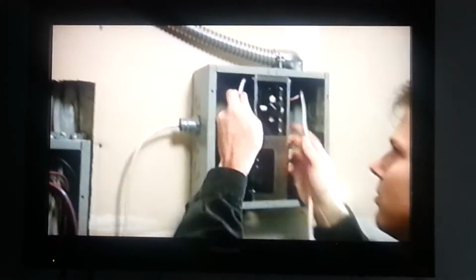Connect the other ends of the wires to the double-pole circuit breaker in the service panel, in accordance with the breaker label instructions. Please note that neutral wires from the generator or manual transfer switch should be passed through the knockouts of the ATS transfer switch to the service entrance panel. Also note that the ATS transfer switch has an enclosure ground connection, if one is needed for code compliance.